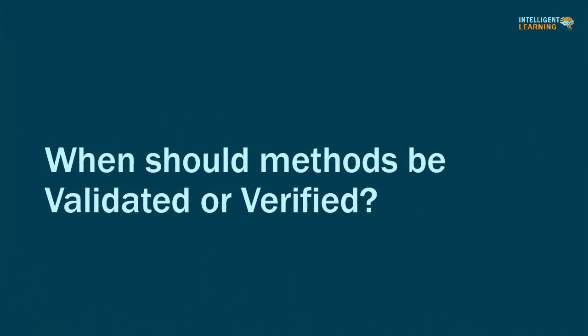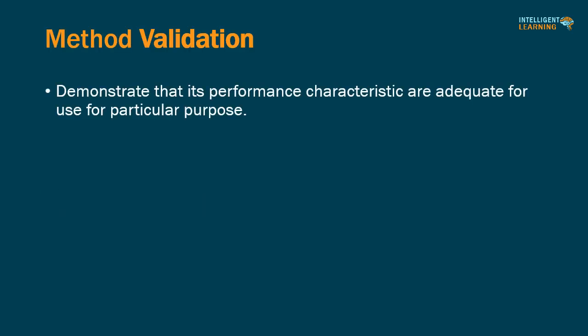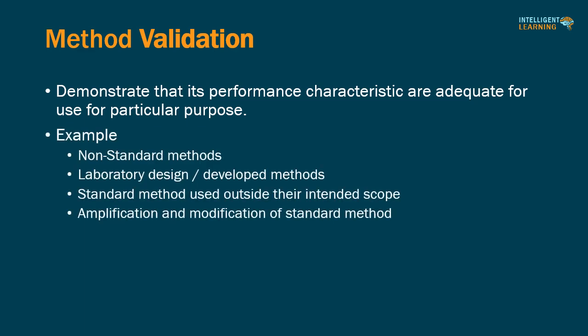When should methods be validated or verified? A method should be validated when it is necessary to demonstrate that its performance characteristics are adequate for use for a particular purpose. For example, a laboratory shall validate non-standard methods, laboratory-designed or developed methods, standard methods used outside their intended scope, and amplifications and modifications of standard methods.